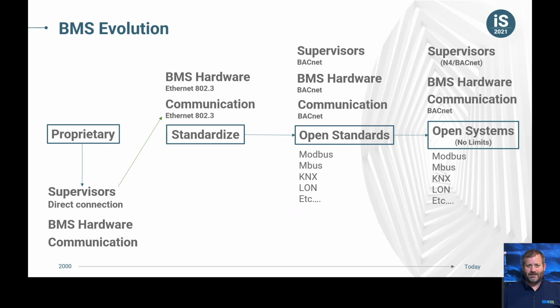An open system is where everybody's standards come together under one umbrella. We see supervisors with N4 and BACnet communicating with the BMS BACnet hardware, with communications on the Ethernet with BACnet. And then we also see integration to Modbus, MBus, KNX, LON, etc. So we see everything coming together under one system rather than multiple proprietary systems. And then to make it truly open, we're bringing in legacy hardware with N4 drivers.